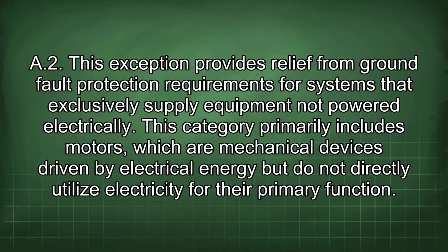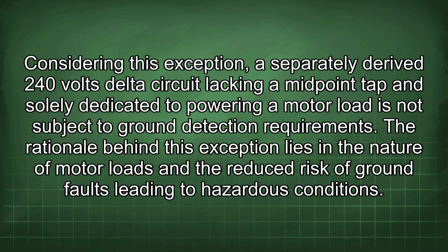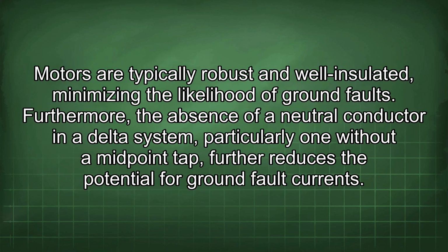This category primarily includes motors, which are mechanical devices driven by electrical energy but do not directly utilize electricity for their primary function. Considering this exception, a separately derived 240 volts delta circuit lacking a midpoint tap and solely dedicated to powering a motor load is not subject to ground detection requirements. The rationale behind this exception lies in the nature of motor loads and the reduced risk of ground faults leading to hazardous conditions. Motors are typically robust and well insulated, minimizing the likelihood of ground faults.